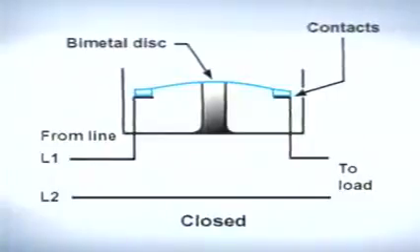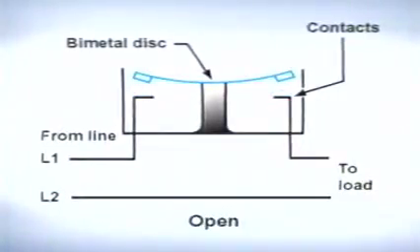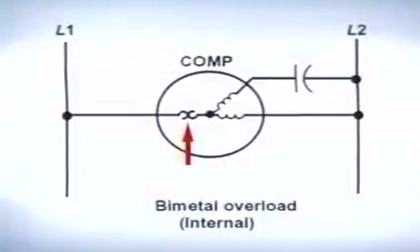When the current exceeds the acceptable level, the heat generated will cause the bimetal disk to warp, causing a circuit to open and de-energizing the circuit. Some line break bimetal overloads are also equipped with devices that sense the surface temperature of the controlled device to provide a more accurate range of circuit protection. The overload is wired in series with the common terminal of the motor.